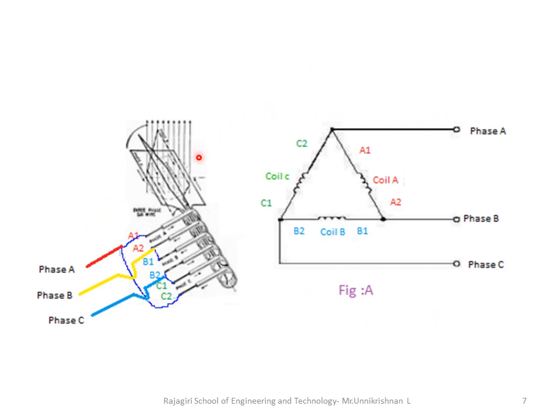Now, as we have said, we will move on to the second configuration, which is a delta connected system. You get the delta connected system by connecting A2 with B1, B2 with C1 and C2 with A1, as shown in the figure. So you can see how we are connecting, and we will get three joins. From each join we will take phase A, phase B and phase C. So this system won't have a neutral point. Only three wires are coming out of the slip rings.